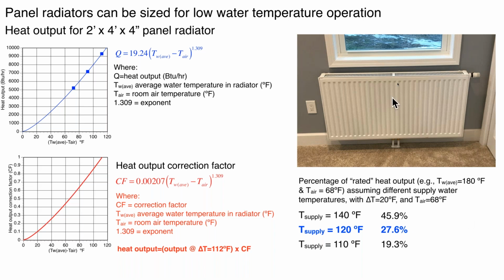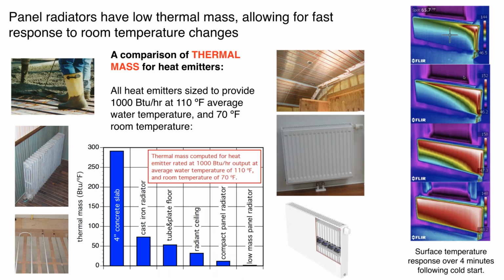And the panel you're looking at here, I believe that is a 4x2, and it's about 4 inches thick. And you can see just 2 half-inch tubes right up through the floor, connect into the bottom. There's isolation valves down here if you ever have to remove this panel. And then up here in the corner is that non-electric thermostatic valve. That is the thermostat in that room that automatically adjusts the flow rate through that panel to maintain that room temperature. Panel rads have low thermal mass.